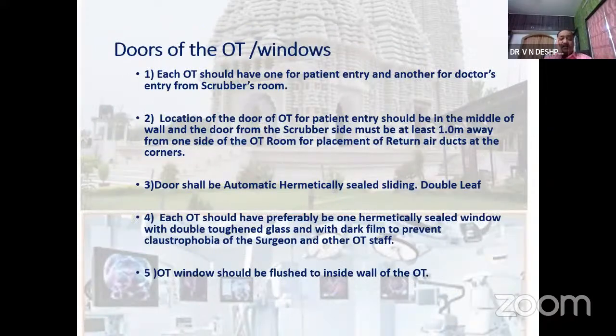The door of an OT, what type of door should it be? Each OT should have one for patient entry and another for doctor's entry. If you are going to have two entries, the first entry should be in the center and the second entry should be at least 3 to 4 feet away from the corner to install the returning air of the laminar flow. Doors should be automatic and hermetically sealed, that means airtight sealed. Sliding doors are preferred, and double leaf doors are also preferred, because swing doors generate a pressure, and the positive pressure inside the OT is disturbed.